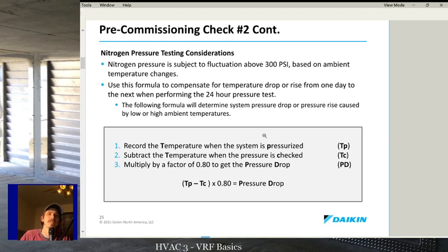But if the whole building is unconditioned and one day it's 70 degrees and the next day it's 40 degrees, you're going to have a pressure difference, right? And you need to know if that's a leak or if that is just a change because of temperature. So record the temperature when the system is pressurized, subtract the temperature when the pressure is checked, multiply that by 0.8 and you get the pressure drop. So this is a good little cheat sheet. So basically your pressure is going to change about 0.8 psi per degree of temperature change.